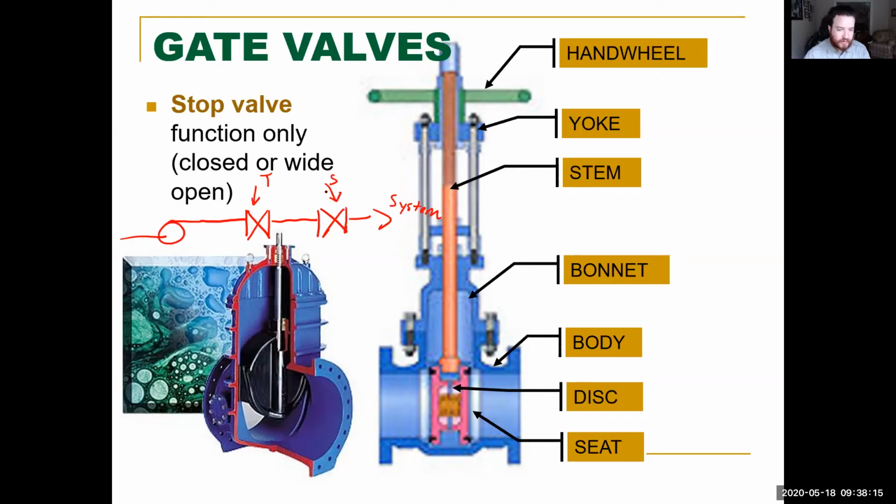So the stop valve will stay as the isolation valve. It will be always fully open or fully closed. You still get that seal. The disc stays protected, and it'll be up in this nice little area. And the throttle valve will be throttled. It doesn't matter if it seals ever again, because you have a sealing valve. You have a stop valve. And the reason I bring this up is there is an instance you'll see this up on the TSES.